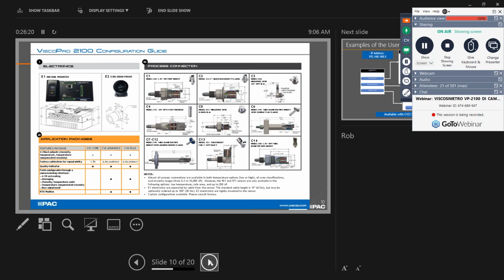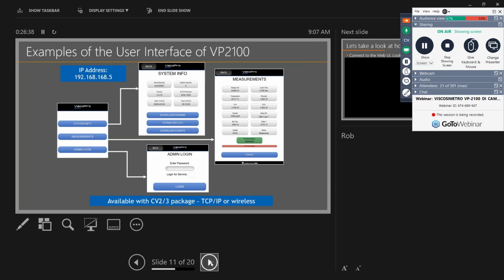One of the features that I mentioned was tying into the instrument using a wireless adapter. To do this, you use what's called our web user interface. So I just want to briefly explain this feature of ours. The web user interface allows you to connect to the Visco Pro 2100 to view live data, download log files, and change any configuration settings that are in the electronics. It has a fixed IP address that you simply need to type into a browser to connect. We have a wireless module that allows you to use your smartphone to connect to it, so you don't have to carry around your laptop throughout the plant while you take a look at the processes. And it's also password protected to prevent users from making any unwanted changes.